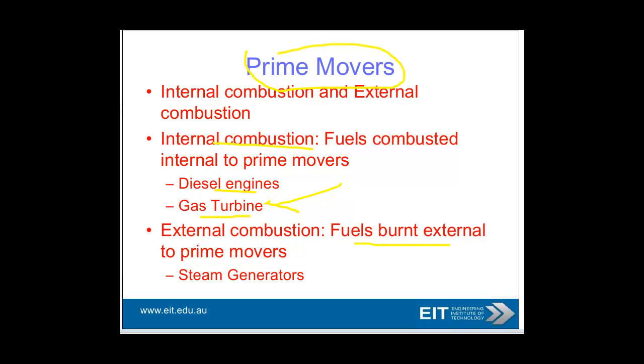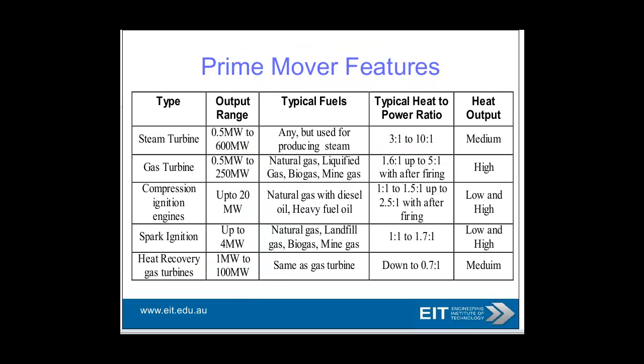External combustion could be fuels burnt external to the prime movers, such as steam generators. Prime mover features is a sort of typical steam turbine. There's a whole range of steam turbine, gas recovery, gas turbines, and just gives you typical heat to power ratio. As you can see, it ranges quite significantly.